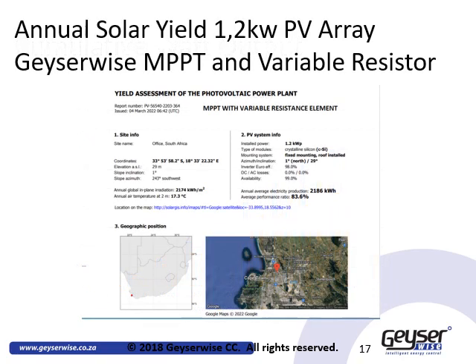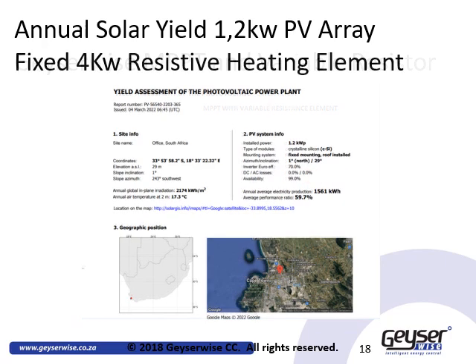Looking at the annual solar yield for a 1.2 kW PV array, the GeyserWise MPPT with the variable resistor gives an annual energy output in the region of 2186 kWh. Compared to a fixed 4 kW resistive heating element, the annual output is 1561 kWh, and this will be even worse when using a 2 kW element on the same PV array.